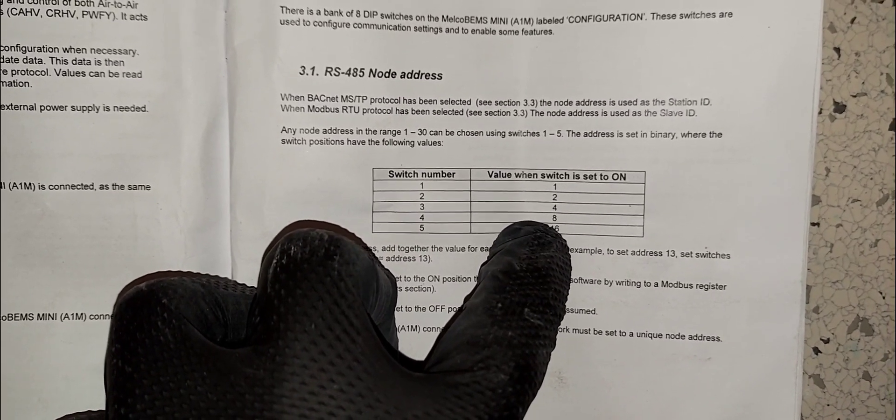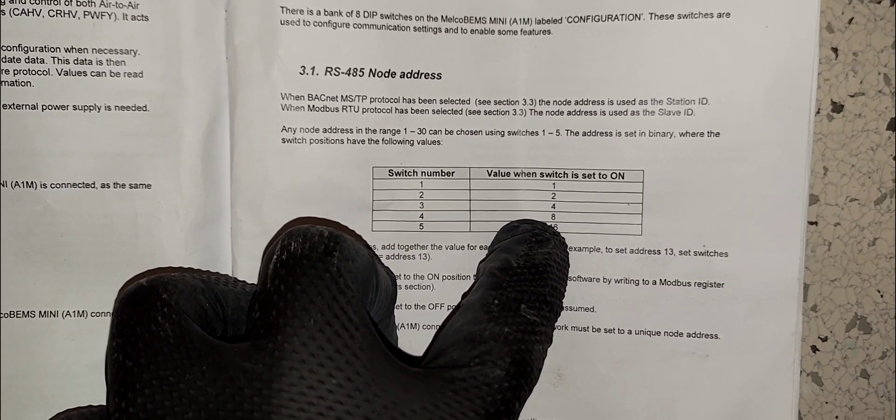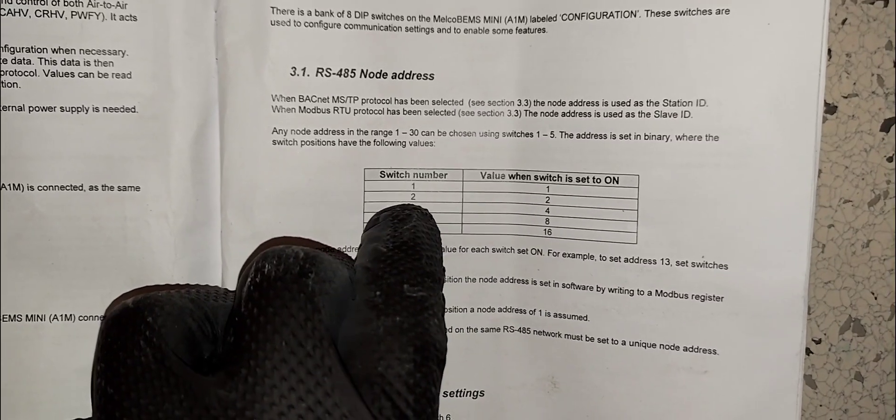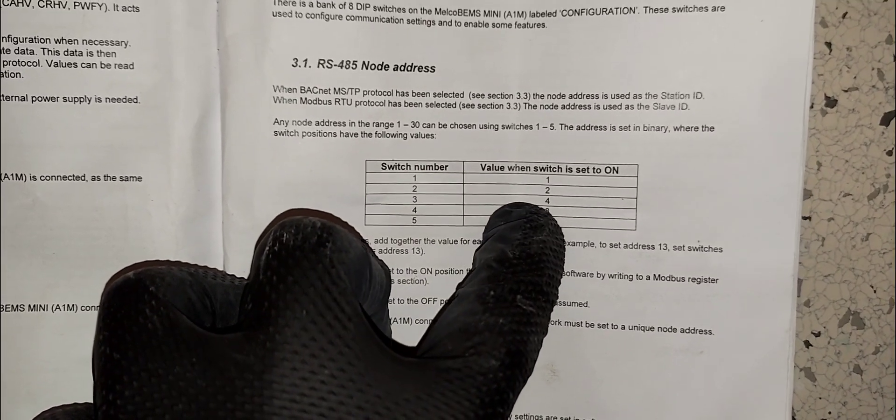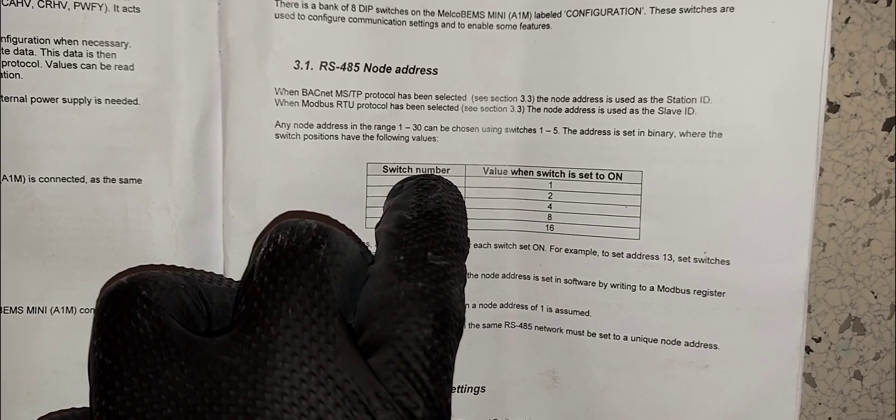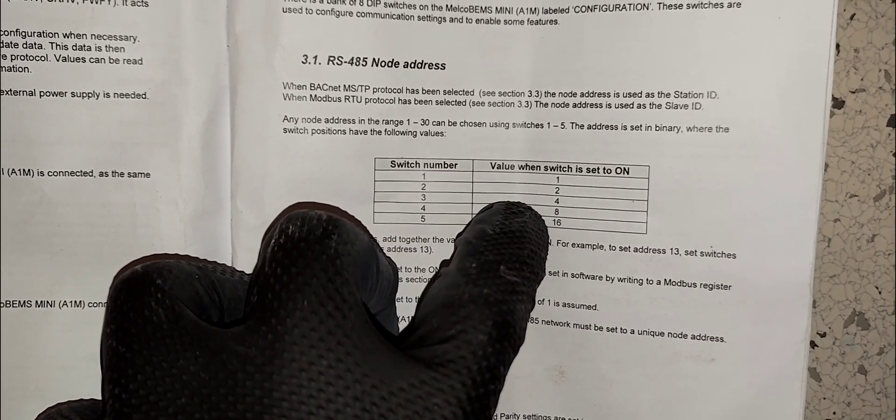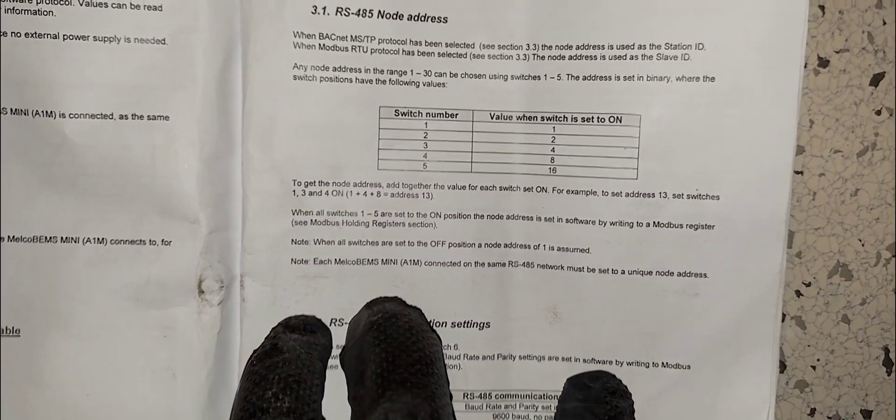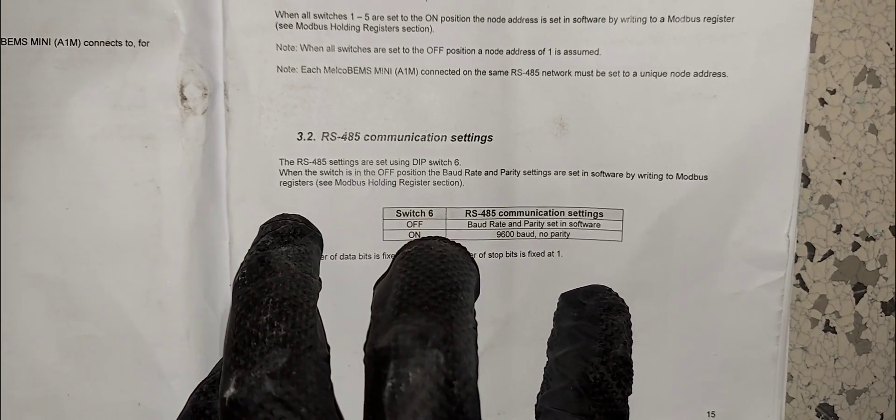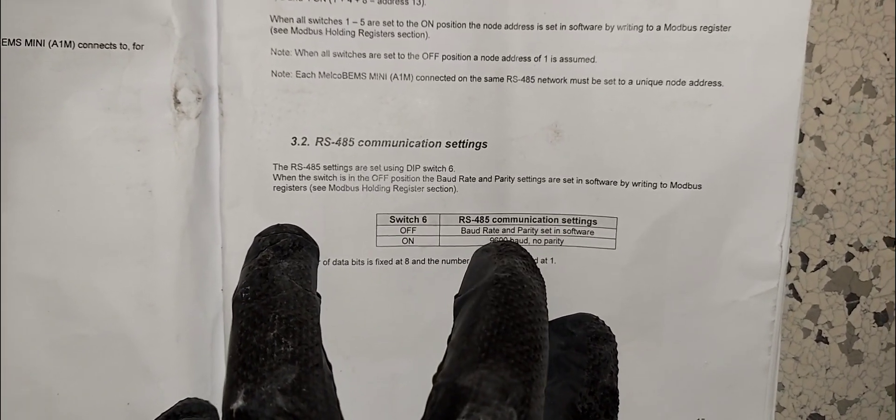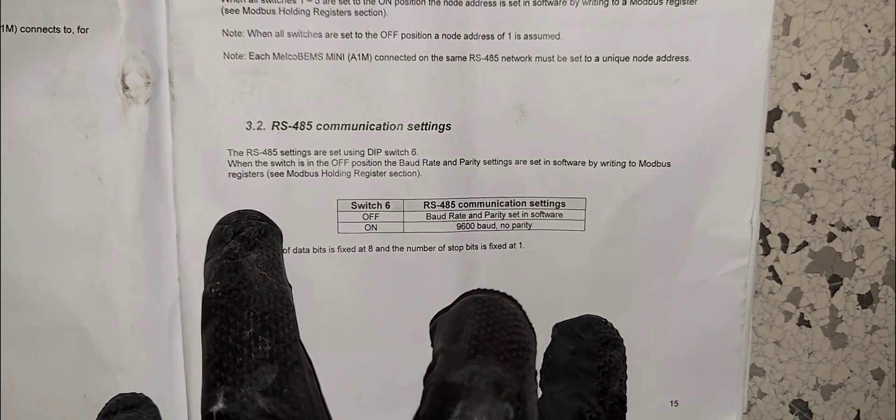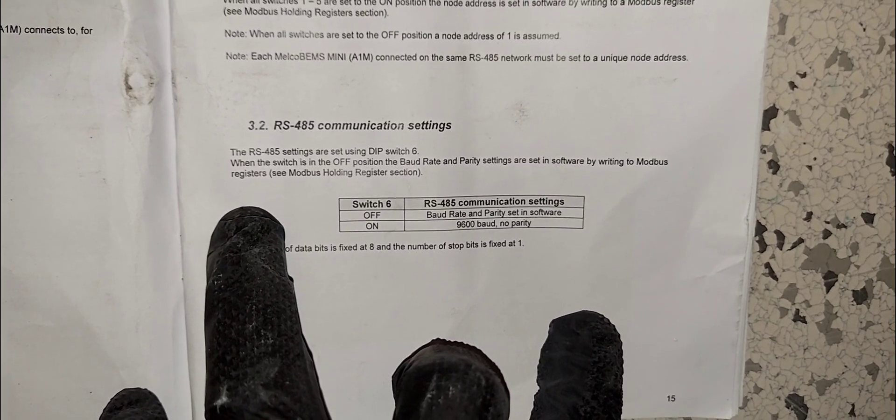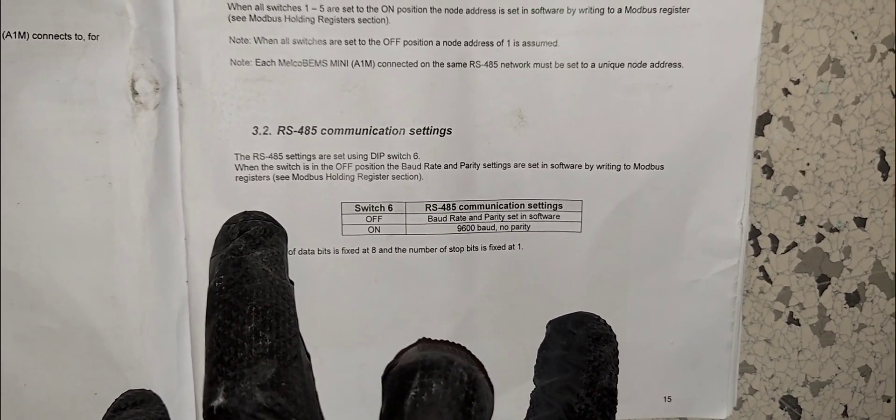If you want address number five, then you will turn switch number three on which is four, and then you turn switch number one on which is one. So one plus four is five. Switch six does the RS485 communication setting baud rate. It's going to be a rather short video guys.